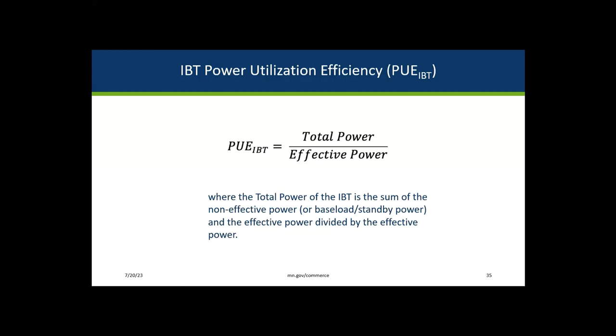When applied to IBTs, the data center infrastructure power load can be considered the non-effective power of an IB system, intelligent building system. Therefore, a similar form of the PUE can be defined for IBTs, where the PUE is the total power load of the IBT. In other words, the sum of the non-effective and effective powers divided by the effective power.